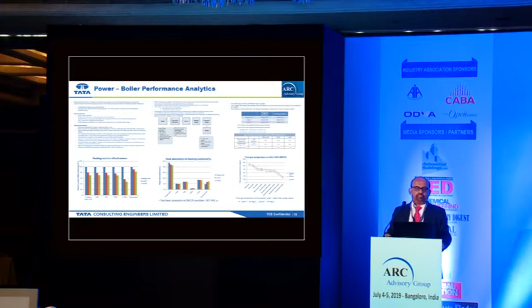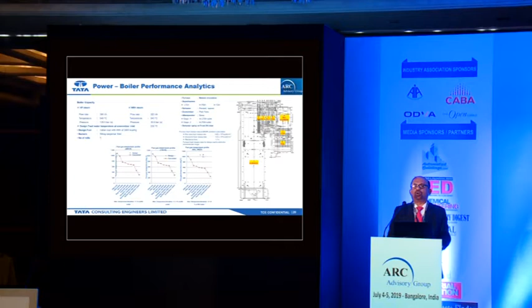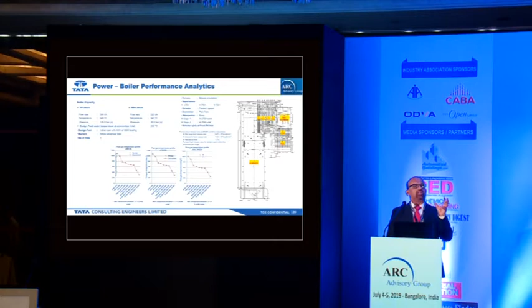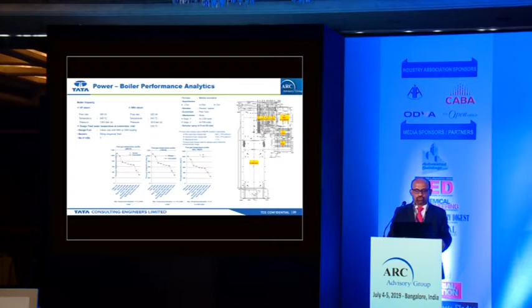We have done this for both subcritical as well as supercritical plants, tested on a 120 megawatt plant, a 500 megawatt plant, and an 800 megawatt plant. Once you have this, you will be able to tell the operators what needs to be done, because every day he gets a different coal from multiple sources, multiple mines as well, and so it is never the design coal that is there at the plant.